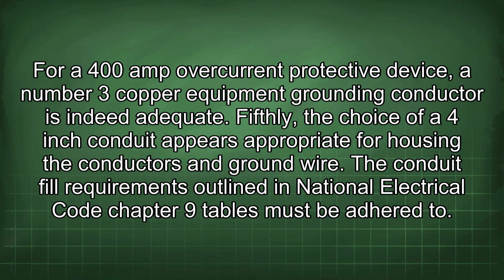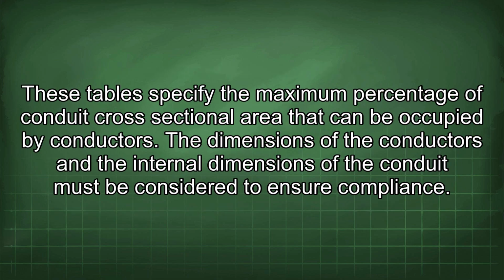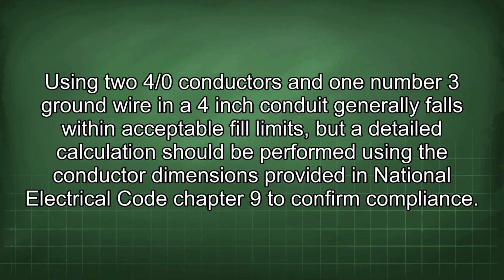Fifthly, the choice of a 4-inch conduit appears appropriate for housing the conductors and ground wire. The conduit fill requirements outlined in National Electrical Code Chapter 9 tables must be adhered to. These tables specify the maximum percentage of conduit cross-sectional area that can be occupied by conductors. The dimensions of the conductors and the internal dimensions of the conduit must be considered to ensure compliance. Using two 4/0 conductors and one number 3 ground wire in a 4-inch conduit generally falls within acceptable fill limits, but a detailed calculation should be performed using the conductor dimensions provided in National Electrical Code Chapter 9 to confirm compliance.